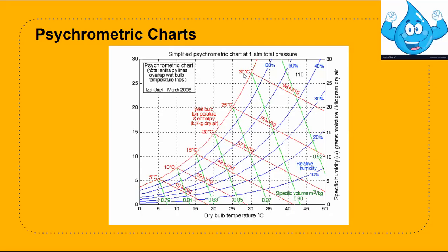Now, what you have here on the saturation curve, the 100% saturation curve, relative humidity that is, you see the temperatures, the wet bulb temperature. So they are in red. And on these lines, which start off with the wet bulb temperature, meaning all of these are wet bulb temperature of 20 degrees Celsius. This is for 25 and this is for 30. You also have the enthalpy values, so the enthalpy values at this particular wet bulb temperature.